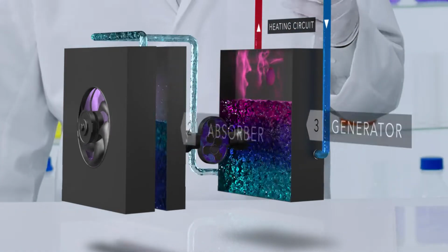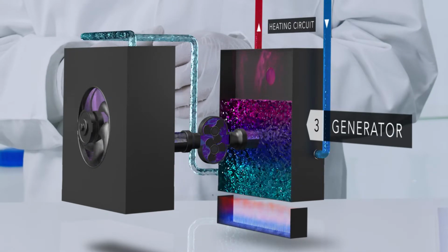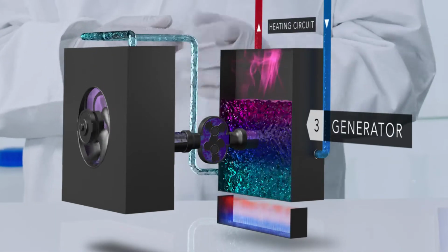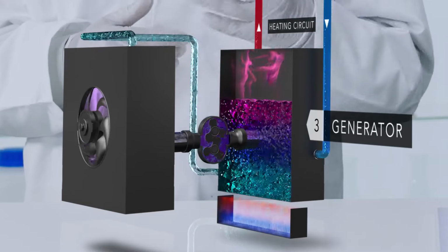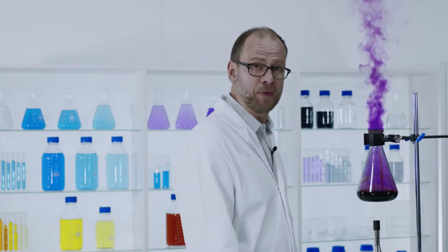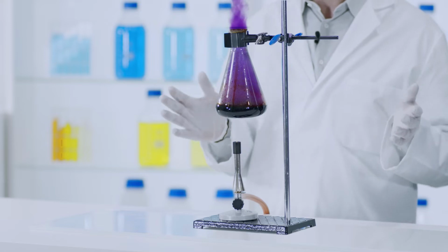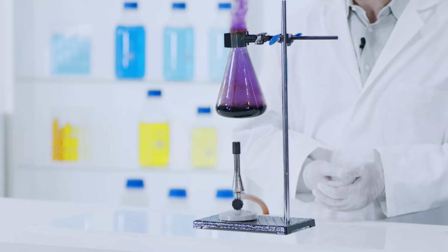In the heat pump model, we see how a pump transfers this mixture to the generator. In the generator, a gas burner is now heating up the mixture. This adds more heat energy to reach the temperature needed for the heating system. This causes the substances to separate again. The water remains liquid, but the refrigerant becomes gaseous. The separated water is then returned to the absorber.